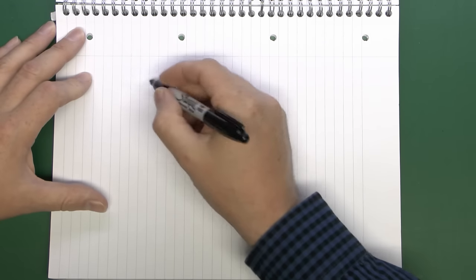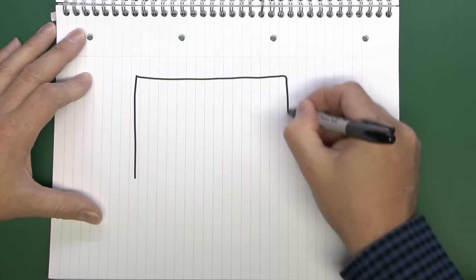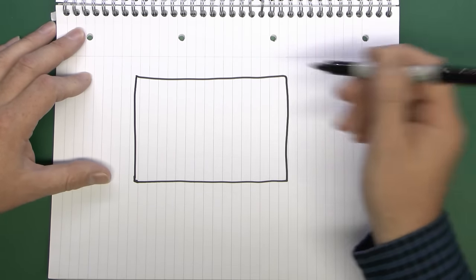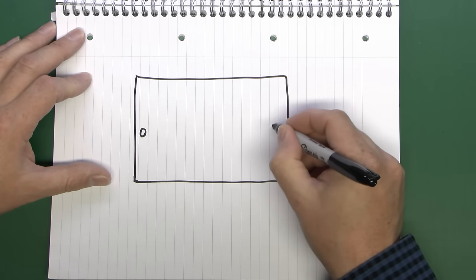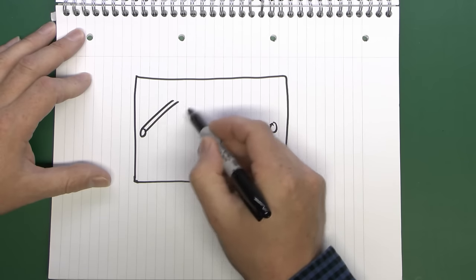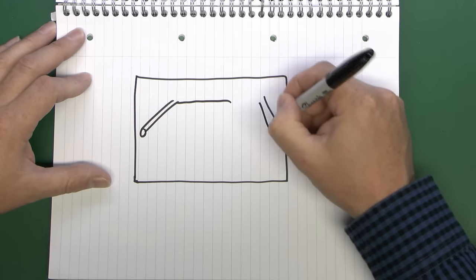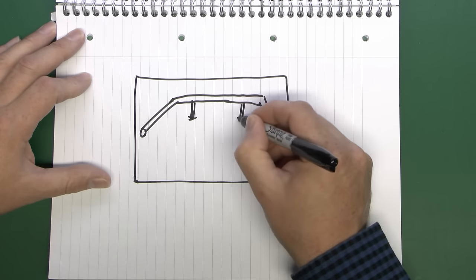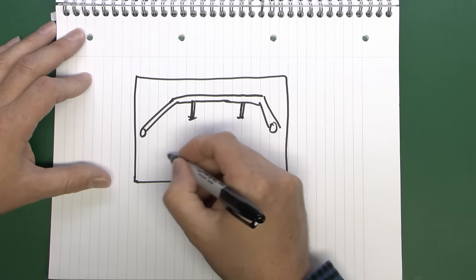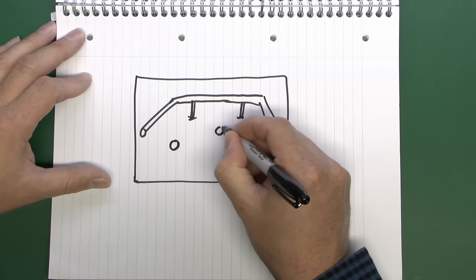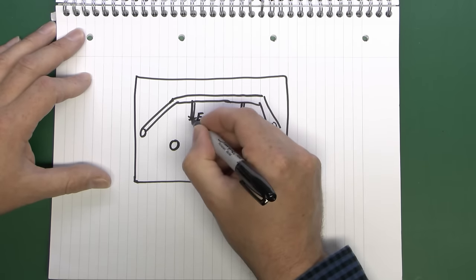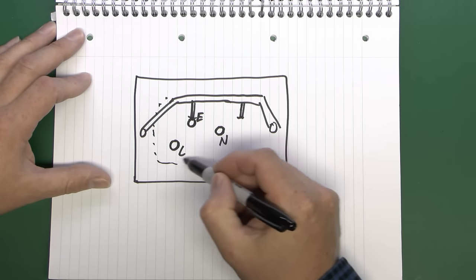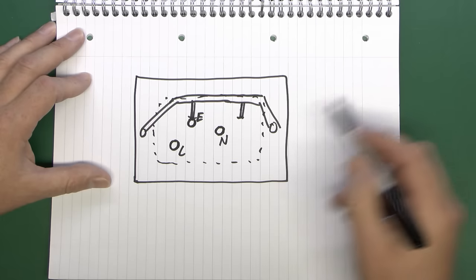In terms of the actual connections, in the back of a typical socket outlet you'll have the three terminals, and they're quite often spaced in rather odd positions. The earth is usually a metal strap that goes between the two mounting holes, with tabs that come down into the individual earth holes. The other terminals are located in rather odd positions — so you have your earth terminal here, the line here, and the neutral over there. Typically on the back you'll have the plastic moulding forming the back of the socket.